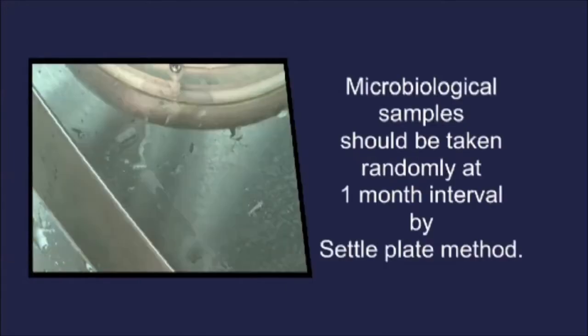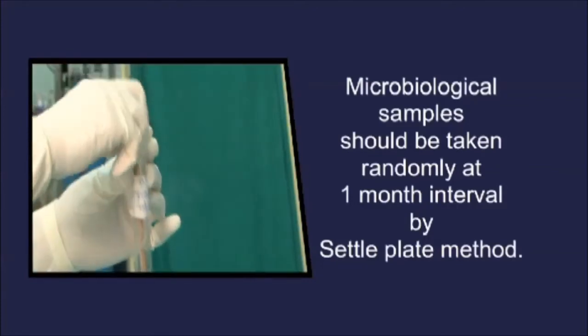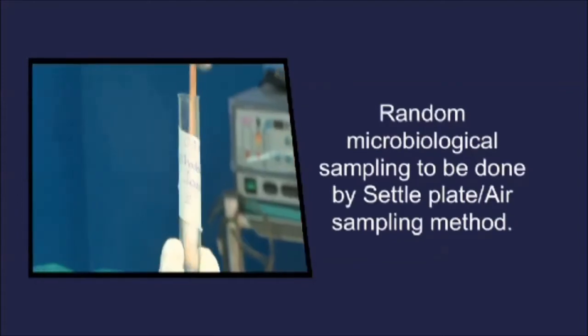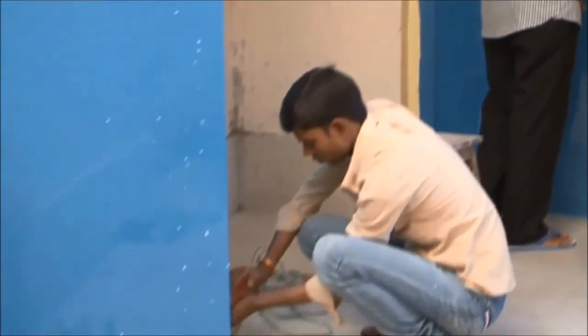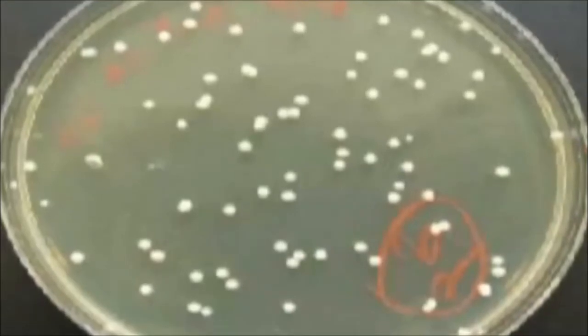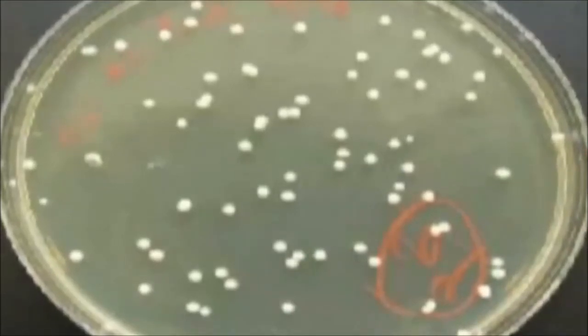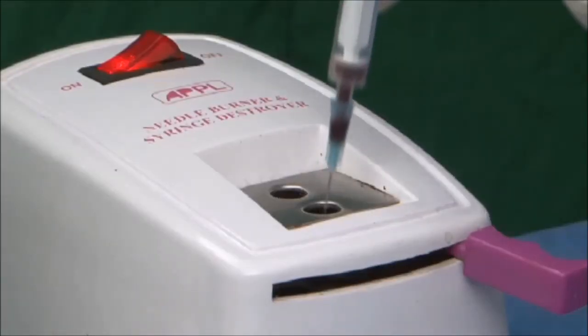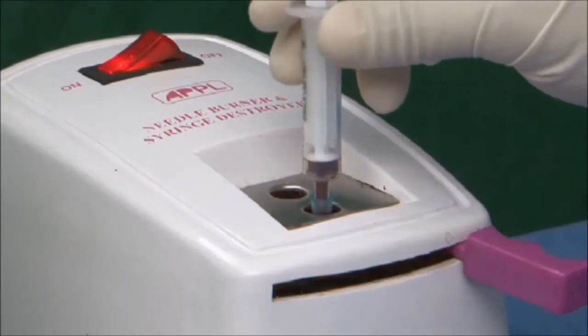Quality control: microbiological samples should be taken randomly at one-month intervals by the settle plate method. Random microbiological sampling should also be done by settle plate or air sampling method following construction, renovation work, or any infectious outbreak. Any colony of fungus or Staphylococcus aureus needs to be reported. If found positive, servicing of the air handling unit and/or AC duct is recommended. There should be arrangements for disposal of biomedical and other wastes in accordance with national and state regulations.